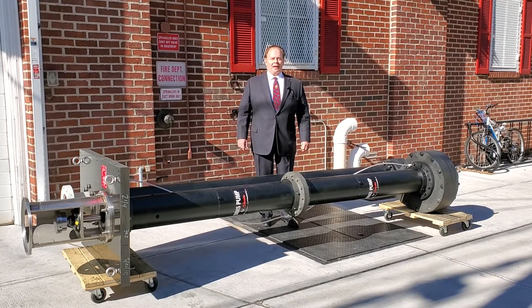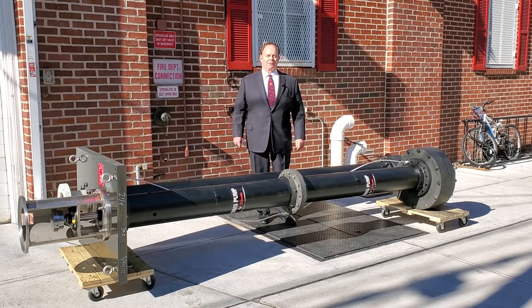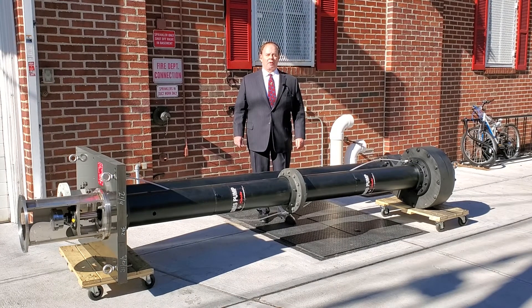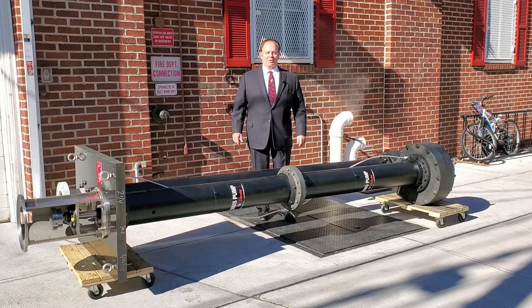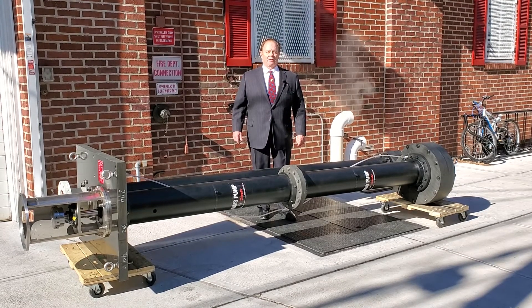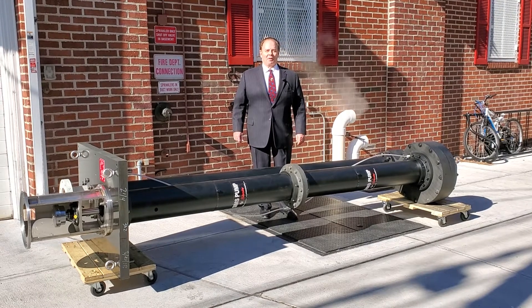This pump was rated at 1150 gallons per minute at a 70 foot head and 1750 RPM with a 40 horsepower motor. This pump will never corrode in seawater. This pump was also designed with a Monel shaft and titanium fasteners with a 316 stainless steel head. Thank you very much.